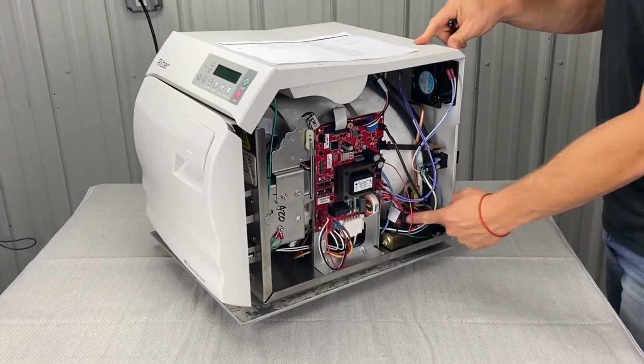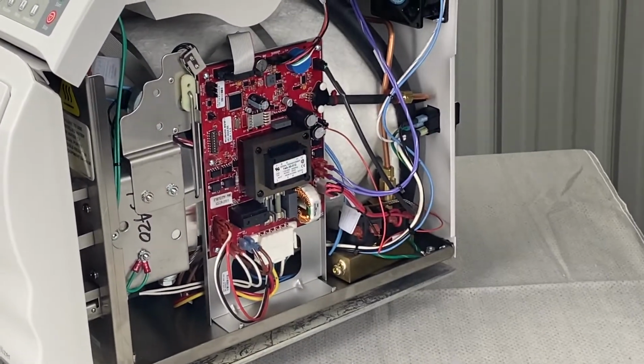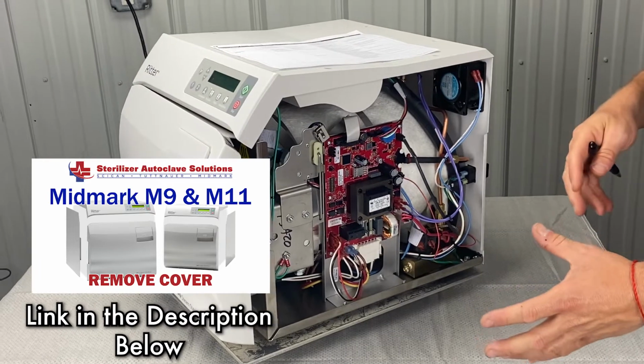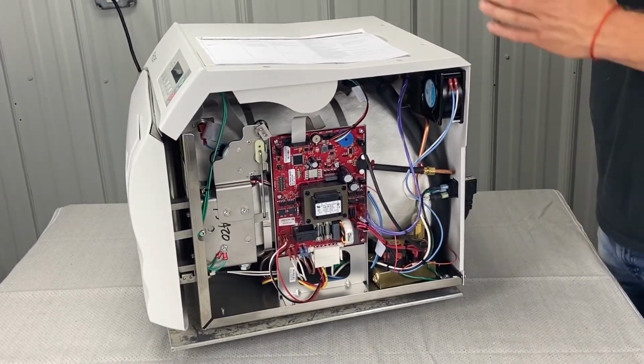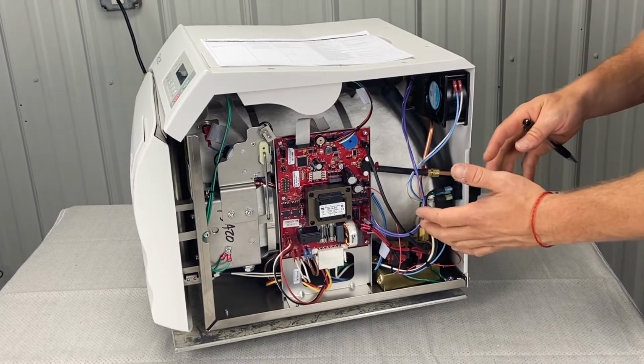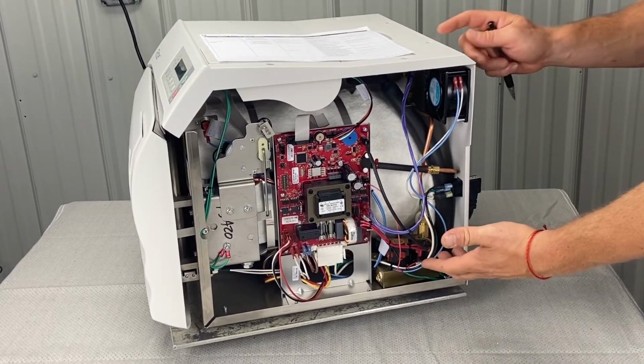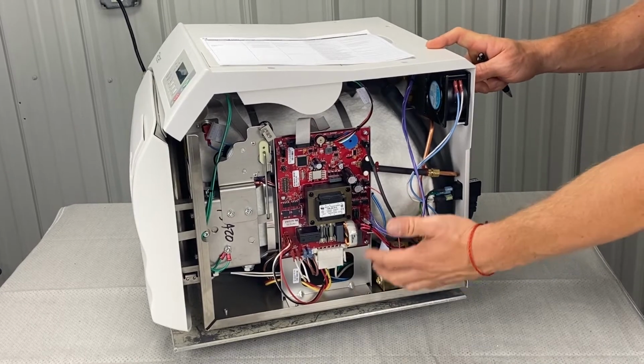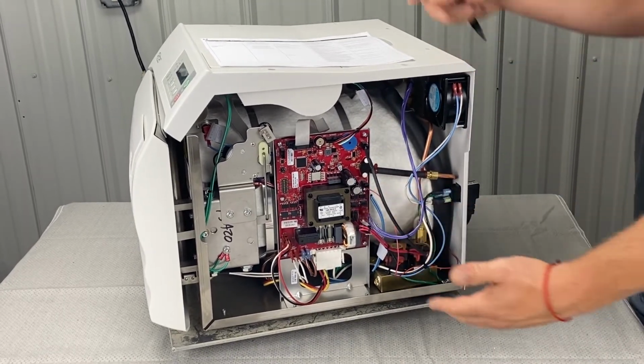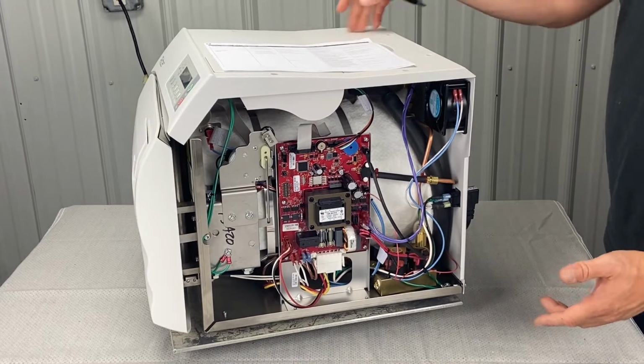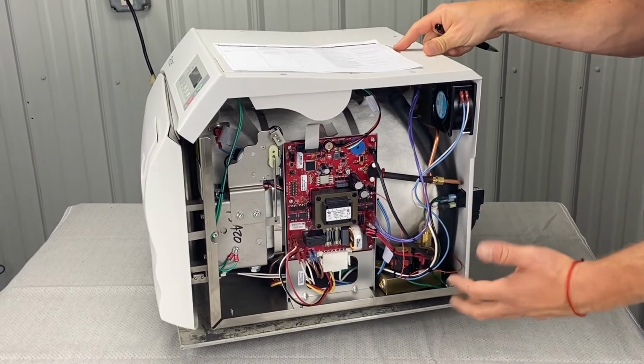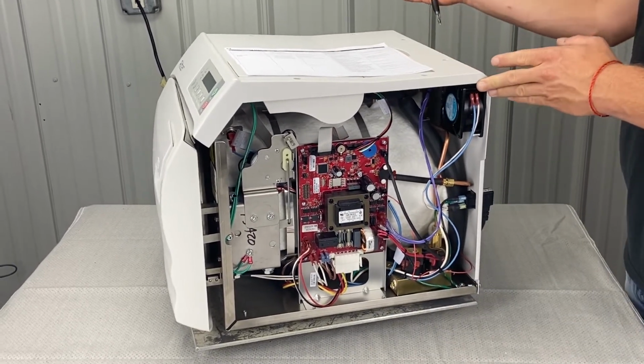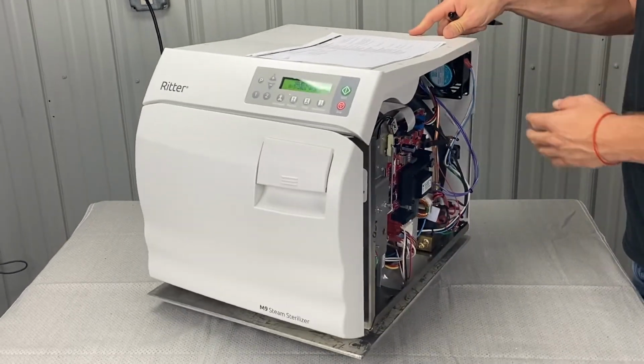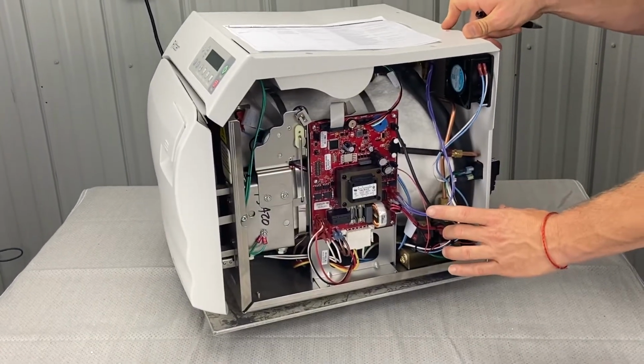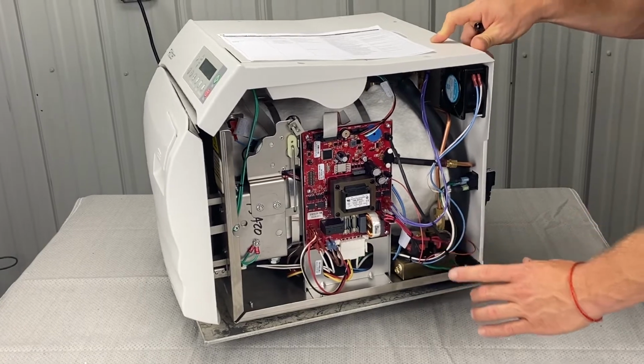You could be leaking at the fill or the vent valve. If you take the cover off and we run an empty cycle, which I don't expect you to do, but if you wanted to, you could then see these things failing in action if they were bad. So if the fill valve is failing while it's heating up, you'll see bubbles in the bottom of the reservoir. If the vent valve is failing as it's heating up, then you'll see water spitting out of the condenser coil. So those are 2 valves that could be failing for this particular error.